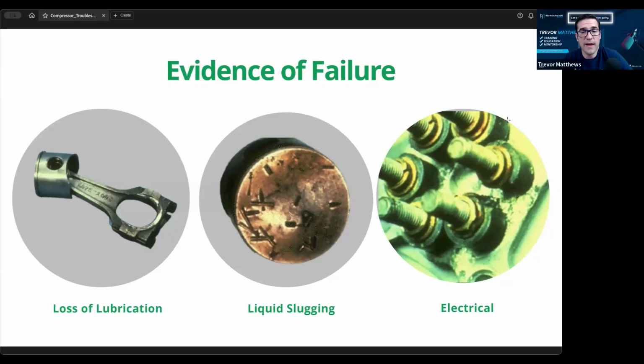Totally agree with that. And if you have a low temp application, on the condenser you might have a CPR, a pressure regulator, so you don't go outside the operating envelope of that low temp compressor. So checking the amps is so key. I think a lot of that is missed out there. It's like, oh well, the superheat is good and the box is down to temperature. It still doesn't mean your electrical isn't outside its range.